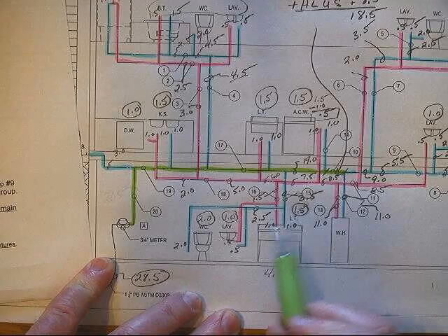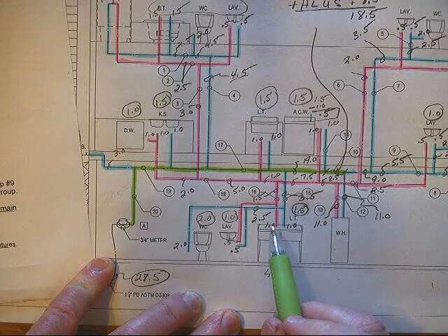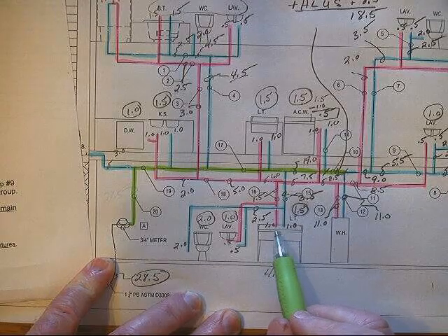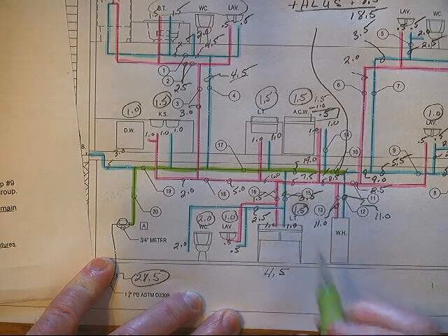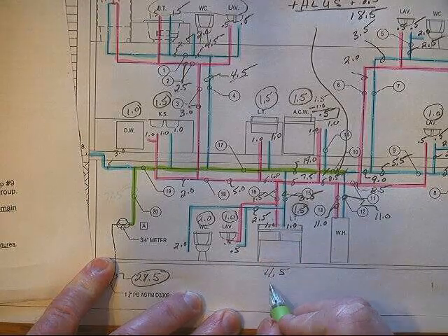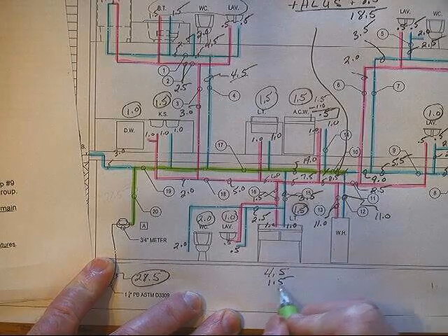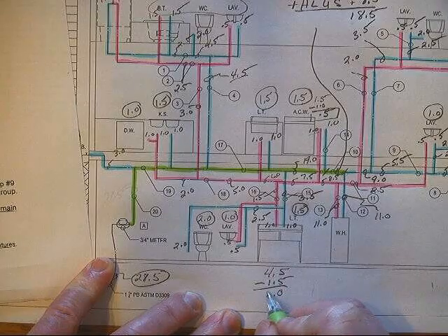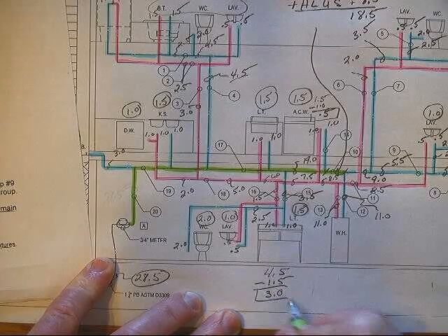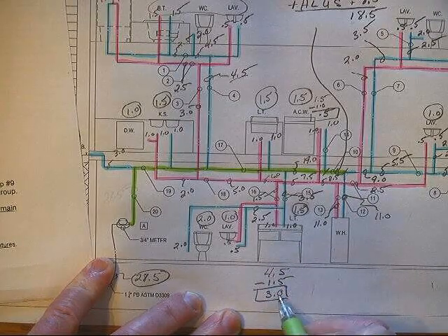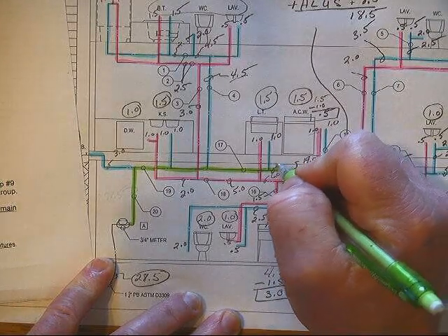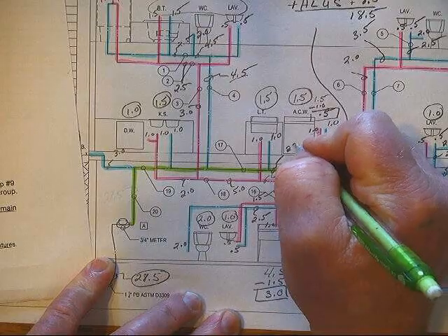We'll subtract any hot load that was served to any of those fixtures, which in this case would be 1 to the laundry tray and 0.5 to the lav, or in other words, 1.5. When we subtract that, we have 3 left over. We'll add that 3 back onto our cold main. We were at 19, we'll go to 22.